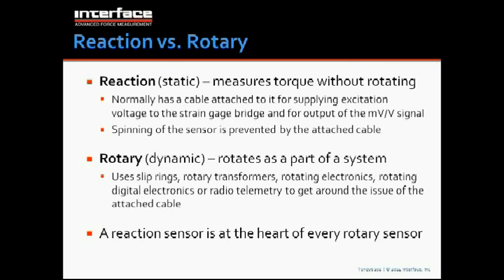Now, in many cases, in tests where there's only a limited amount of rotation, a reaction sensor can actually be used. If you imagine you have a valve test where you're twisting the valve back and forth through 60 degrees, for example, you can easily use a reaction sensor for that measurement. The one caveat is you would have to make sure that the cable doesn't wear out as it wiggles back and forth during the test, and so some method of strain relief for the cable needs to be in place.